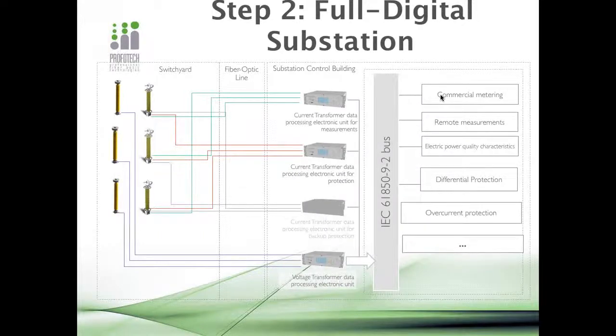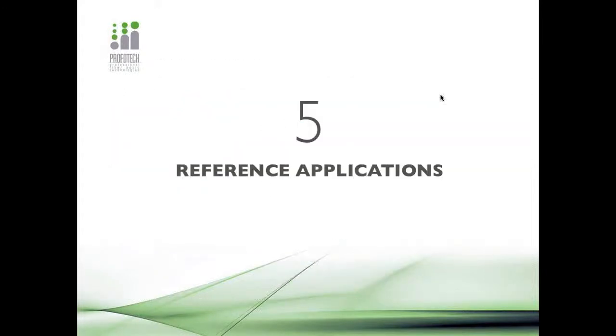And referring to the next slide, you can see that there are more of them. We add one for protection, and we would probably add another one for redundancy protection, but we don't need to install any more primary sensors. We just install these 3 phases of current transformers and voltage transformers. So we just add some electronic modules in the control building. And in this case, we have the interface for any secondary devices like protective relays, some control automation, and, as I said, power quality monitoring and revenue metering.